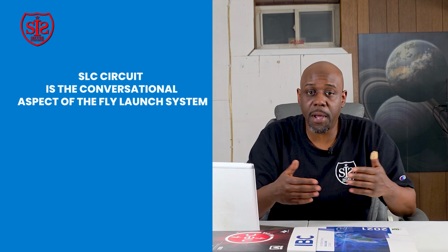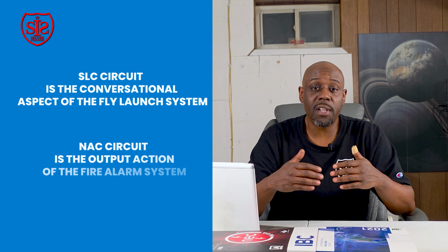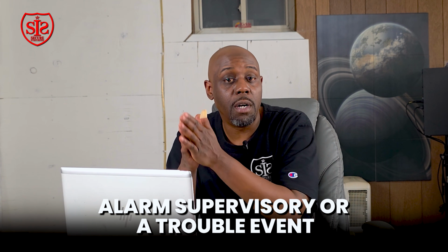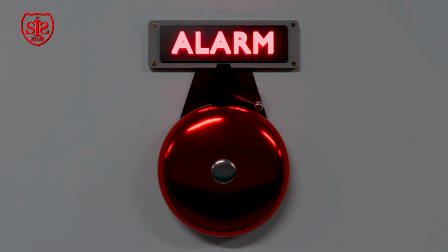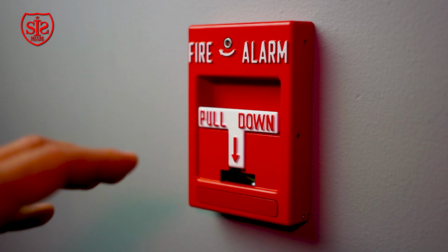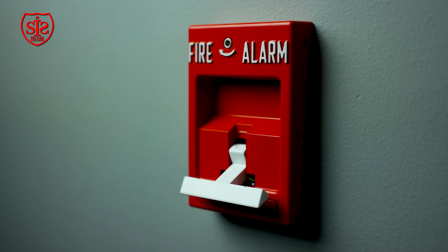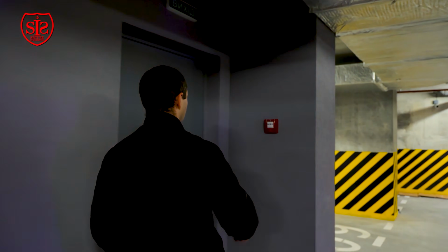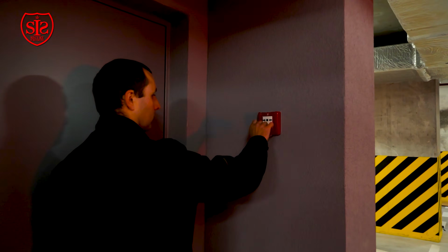So some things I try to teach technicians coming up when it comes to an SLC or a NAC circuit. The SLC circuit is the conversational aspect of the fire alarm system, and the NAC circuit is the output action of the fire alarm system. This is the guy that's going to react off an input event, whether it be an alarm, supervisory, or a trouble event. You can program it to do whatever you want, but usually on an alarm event, it's going to react, it's going to yell, it's going to make some type of noise, enunciation, it's going to let the people know that there's some type of emergency event within this building, and you may need to get up out of here.